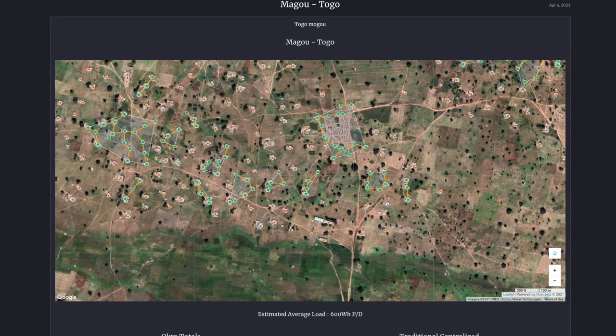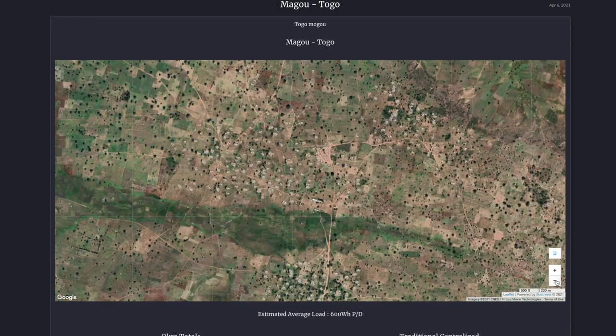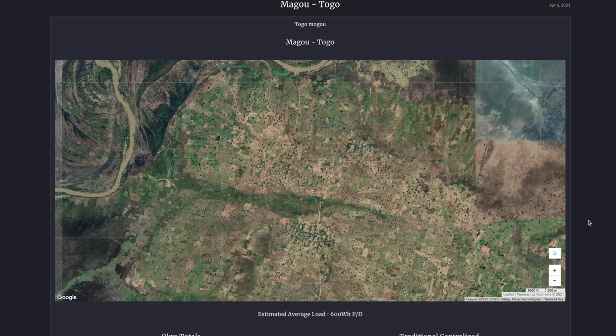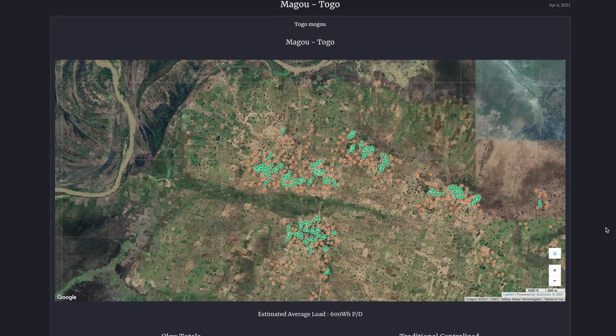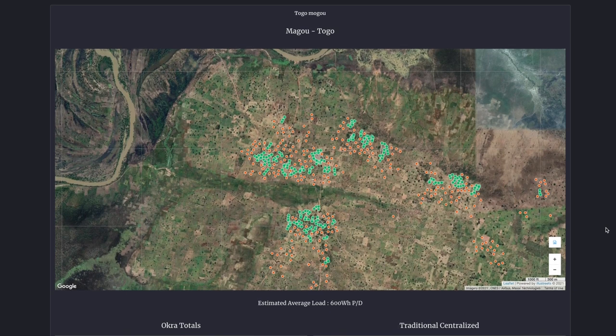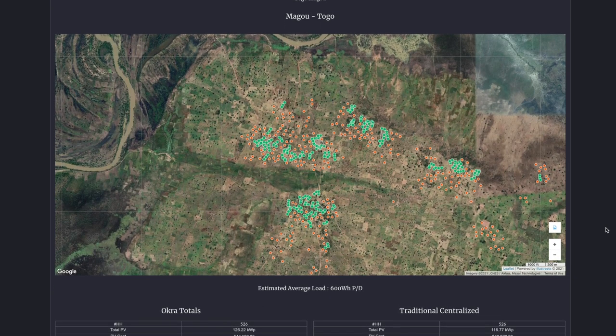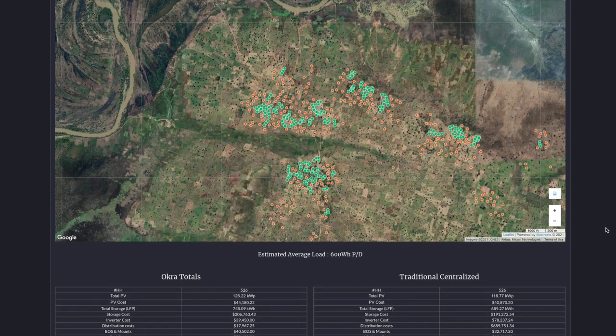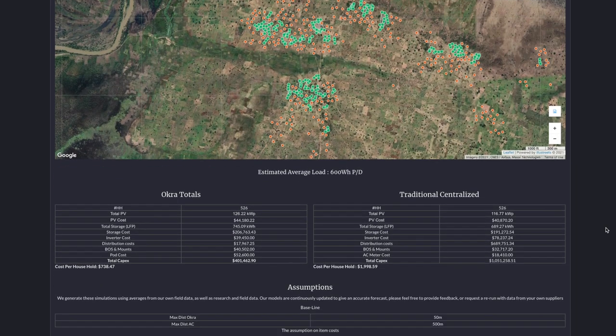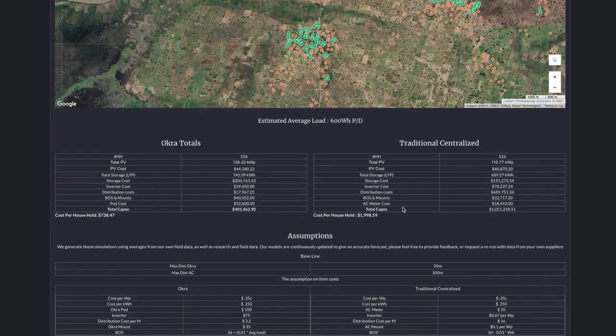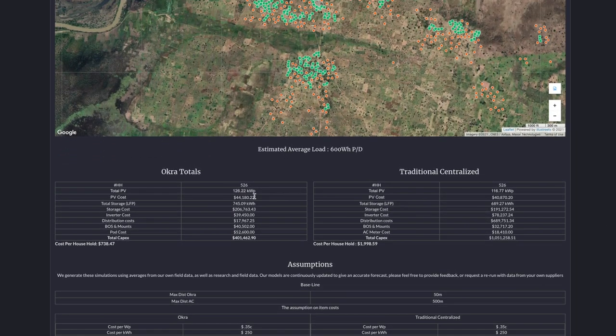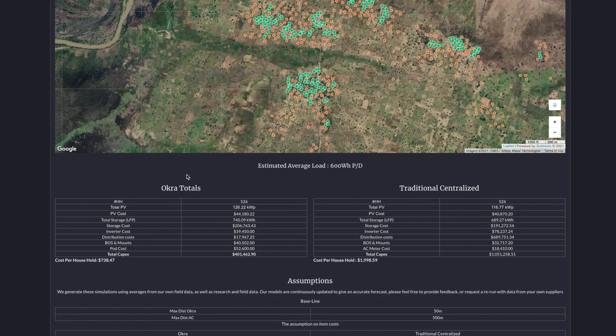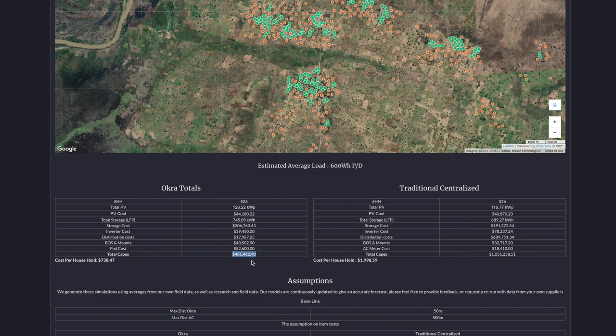But this cluster here, six households, it's recommended to interconnect them into a mesh grid using our Okra technology. Bringing all of that together, we can rapidly size a pipeline for you. We've got 526 households that have been mapped, and the least cost of electrification tool estimates that for 600 watt hours per day average load, there's $400,000 of capex investment that's required.